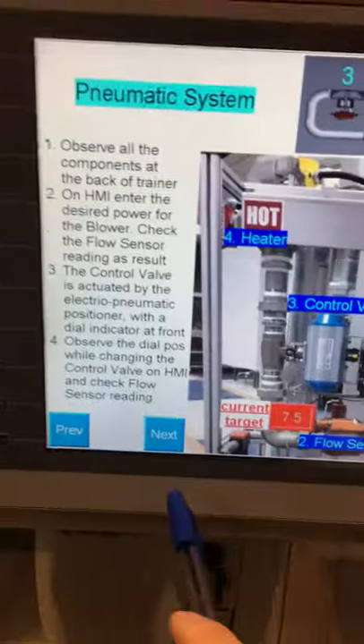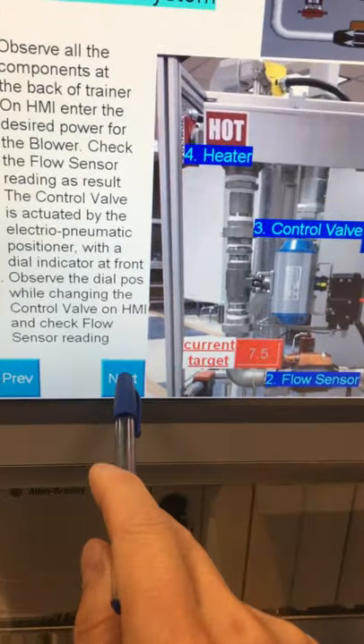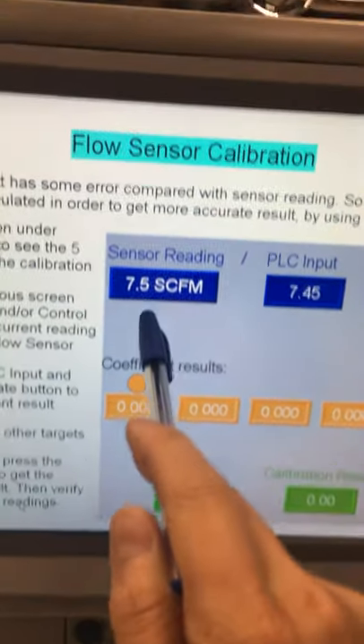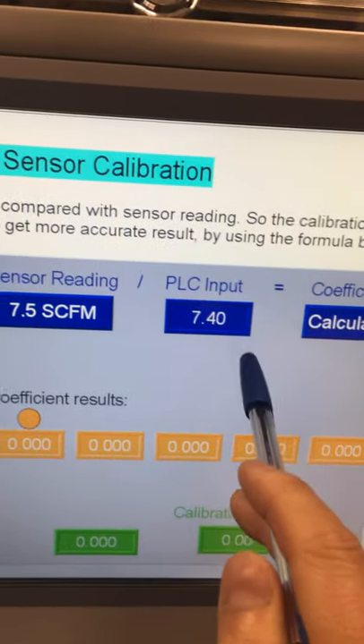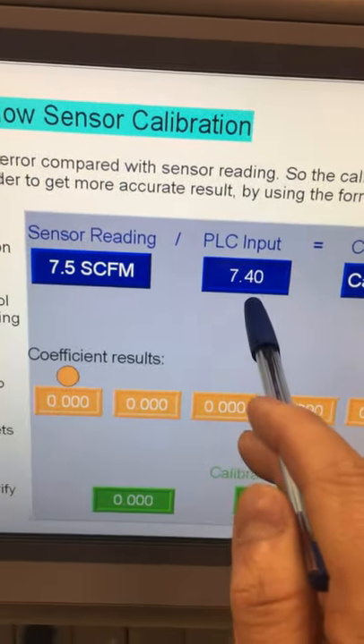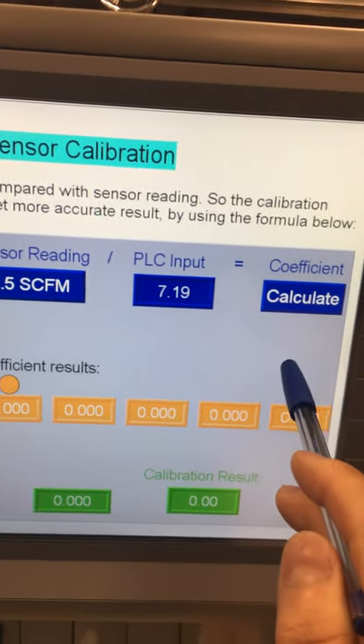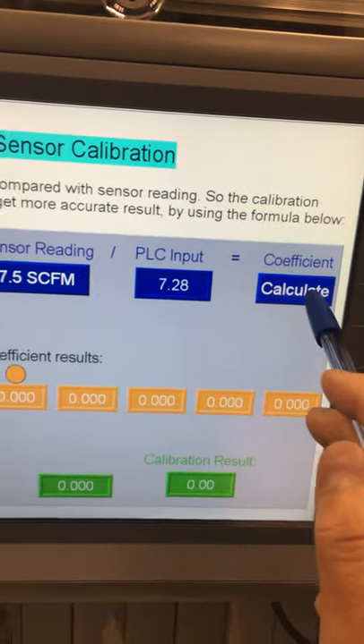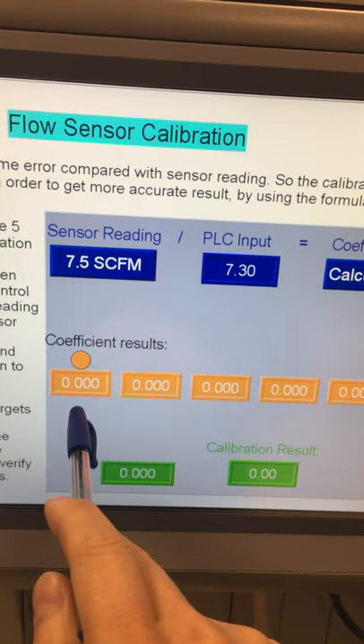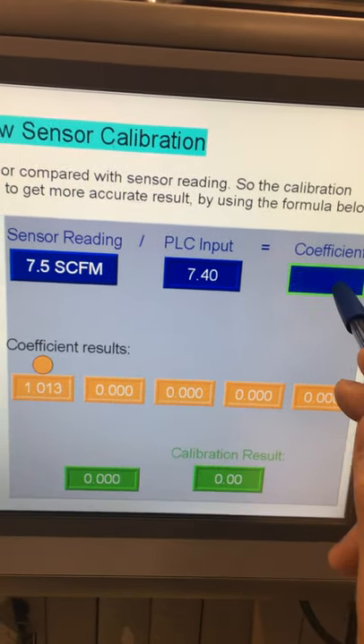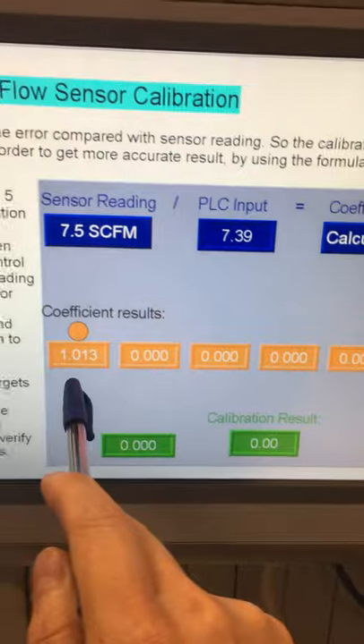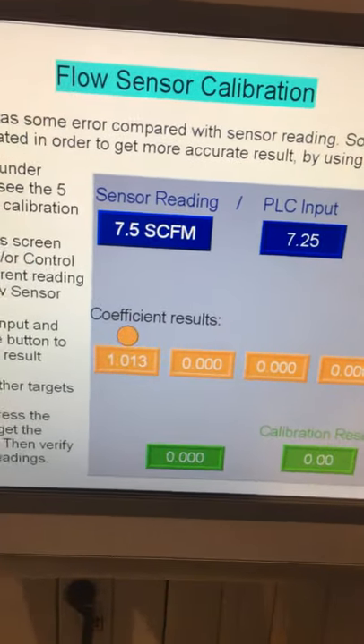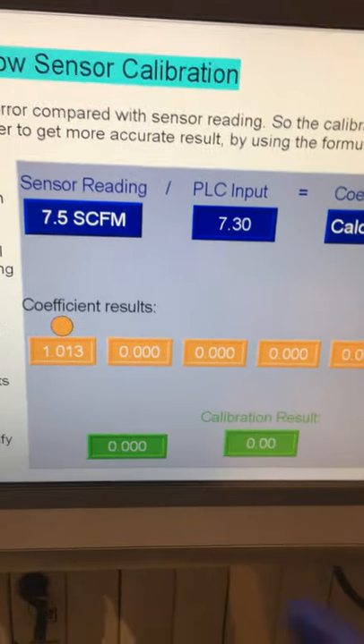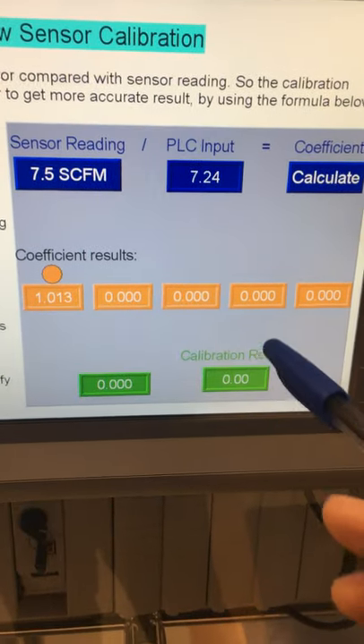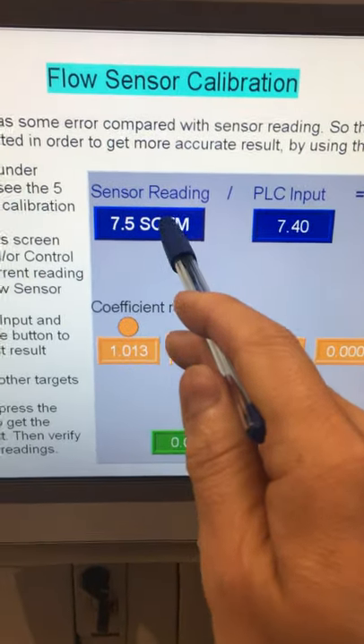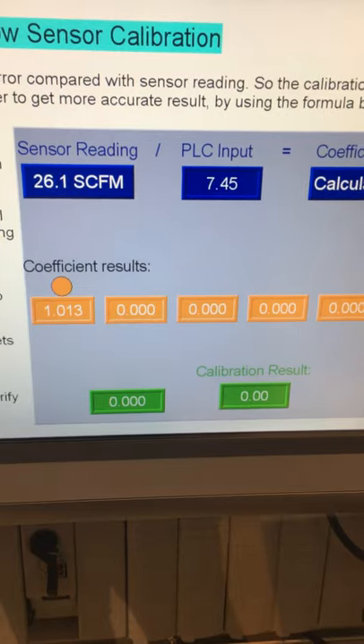So then we need to go to the next screen. Because we reached the target, you can see the sensor reading 7.5. On the PLC, it's very close, right, but not exact. That's why we need to calibrate. If we press this button, this first factor will be calibrated. Then you can see it's 1.013, right? So that's the first result we got. Then we need to press this button to see the next target.